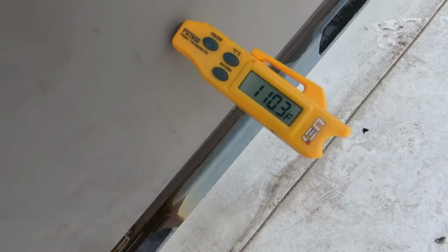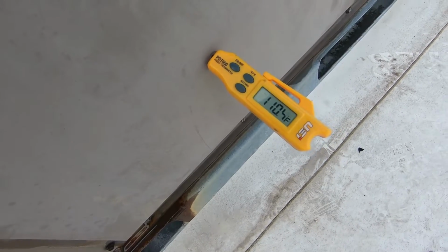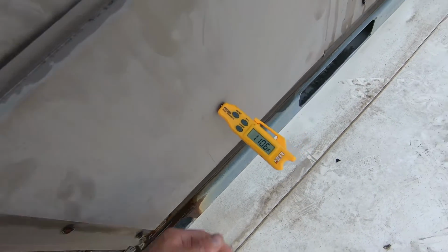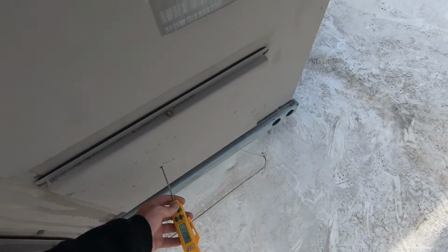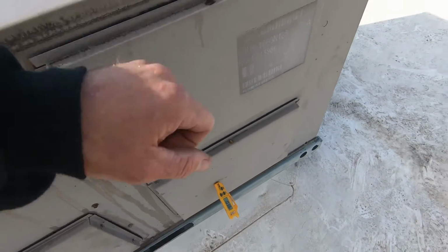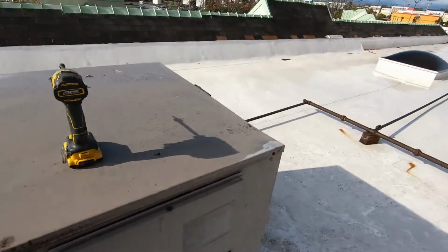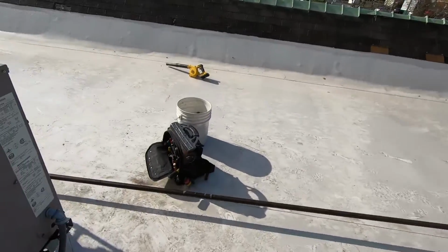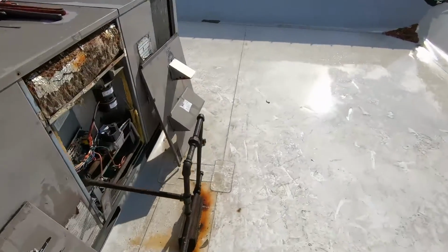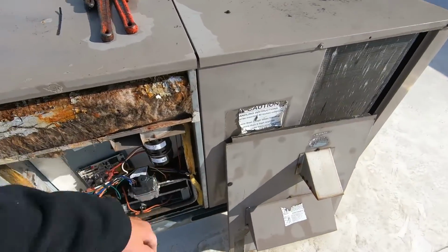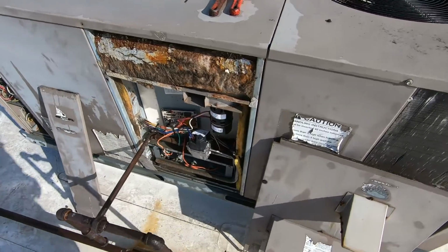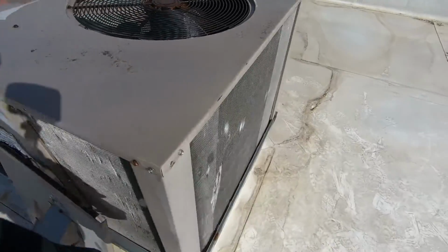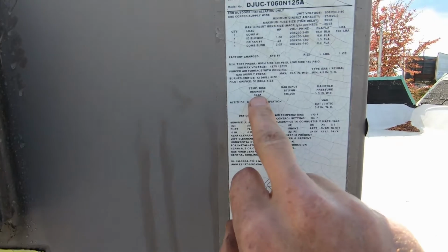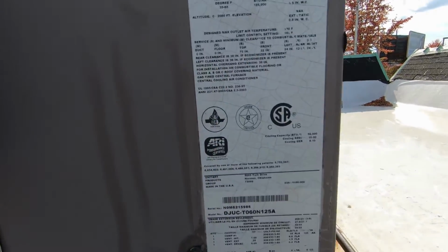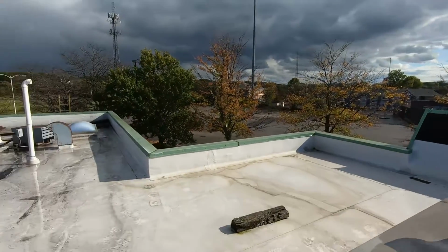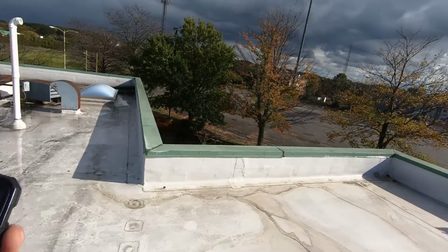All right, 110. Let's get our return temp. Should be around 70. It was reading 67 when I went in there, which in my opinion did not justify an emergency no heat call, but when you're on call, you must go. Let's see, temp rise, 35 to 65 degrees. We service these units quite regularly, so I'm not gonna bother checking gas pressure.